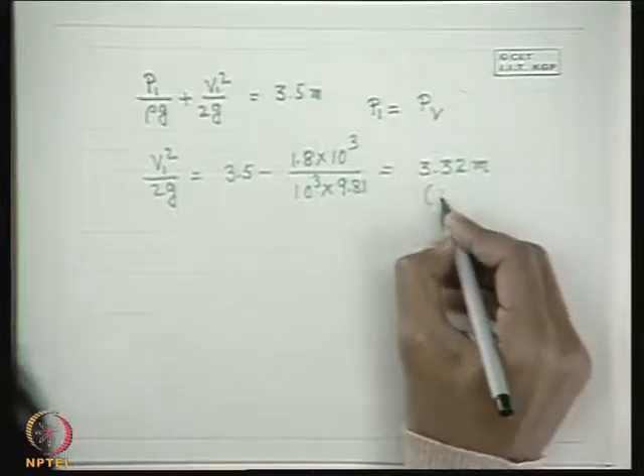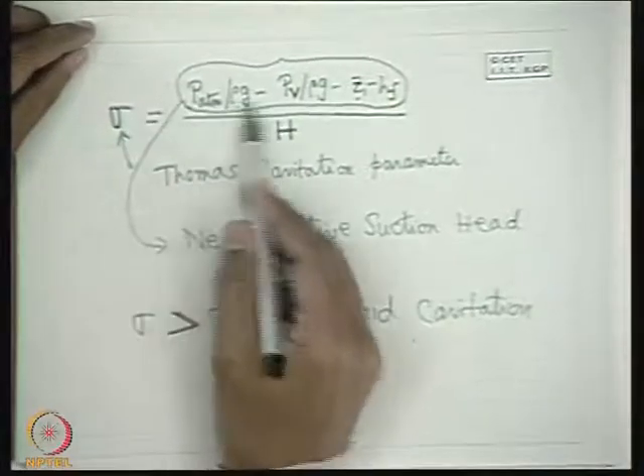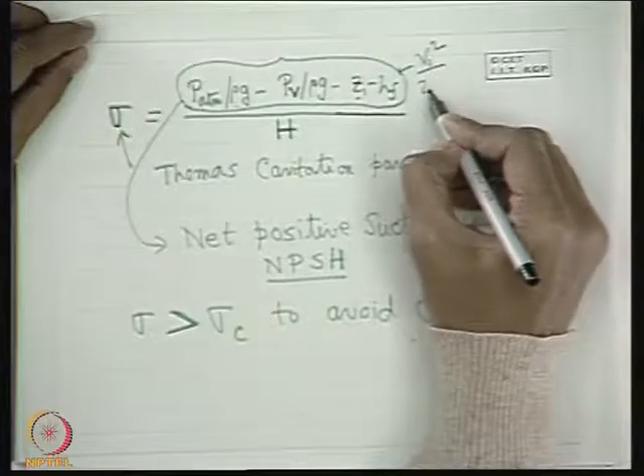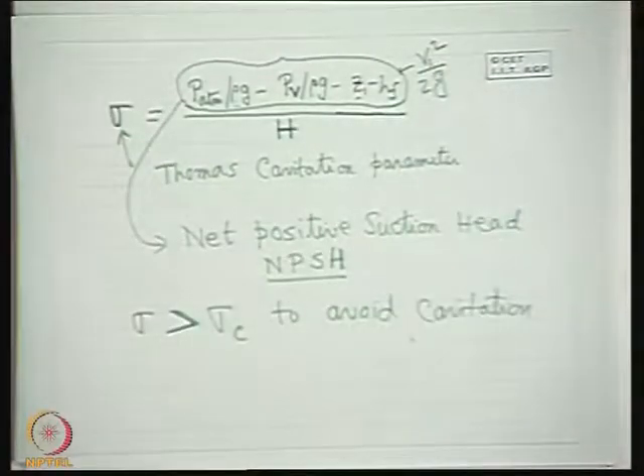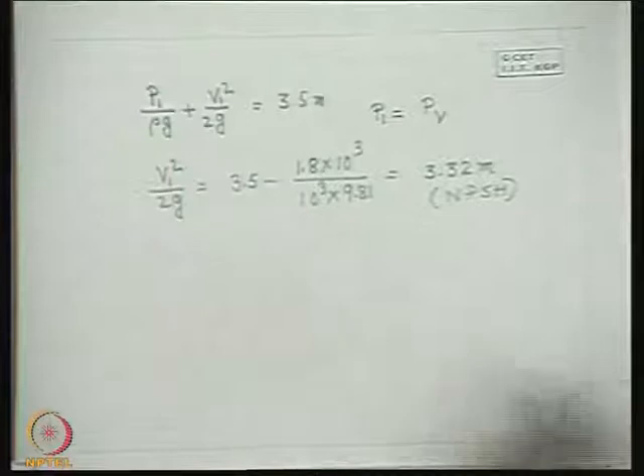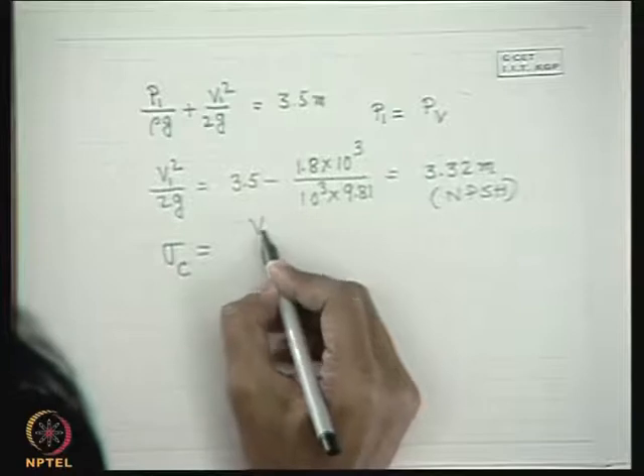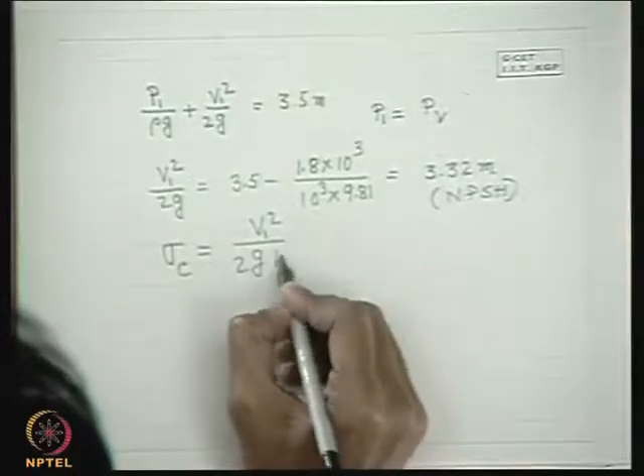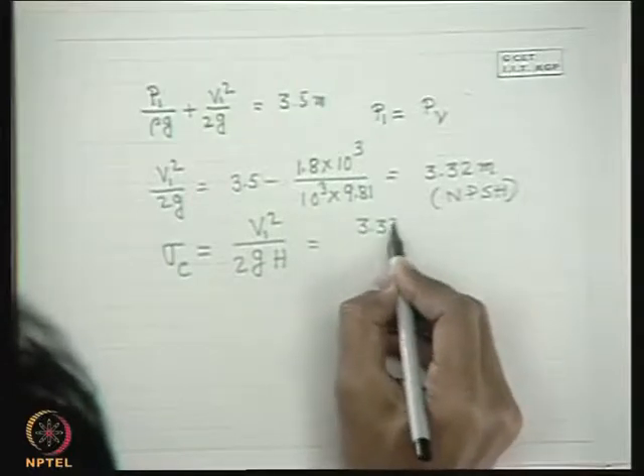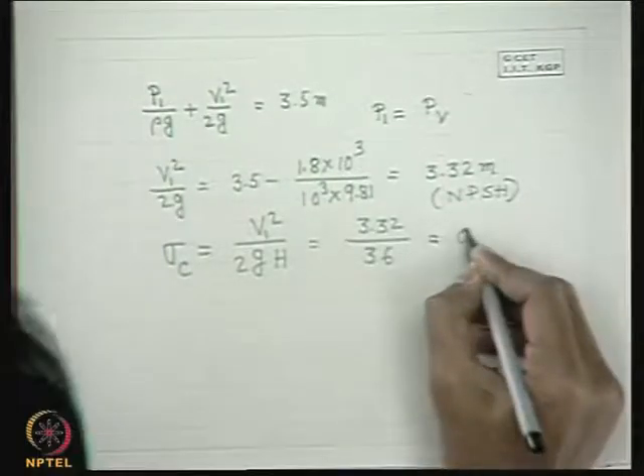This value of V₁²/(2g) = 3.32 meters is the Net Positive Suction Head (NPSH). The critical cavitation parameter σ_c = (V₁²/2g) / H = 3.32 / 36 = 0.092.